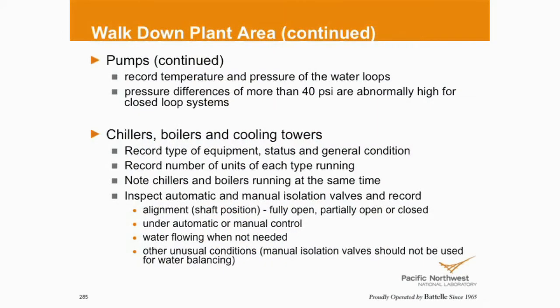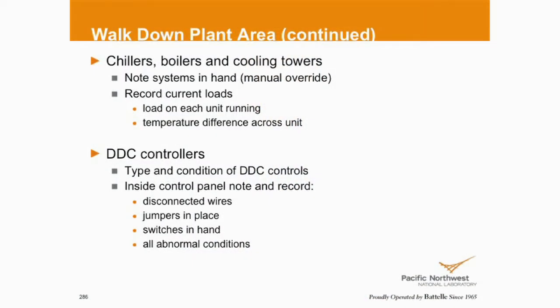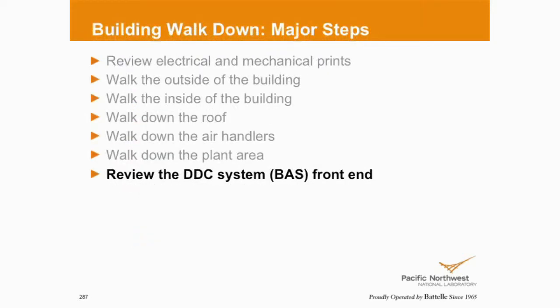Automatic valves should be automatically working and should be closed if the boiler or the chiller that's serving is off, and I should not be flowing water through that boiler or chiller. How do I know if it's flowing water? Look at the temperature gauges right there in the plant, or look at your BAS, your trended data. We've talked about this: systems in hand mode when they should be in automatic, or manually overridden on the BAS.